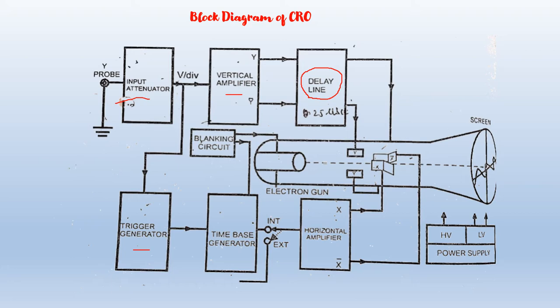The next block is the Time-Based Generator. This produces a sawtooth waveform that is used as the horizontal deflection voltage of the CRT. The rate of rise of the positive-going part of the sawtooth waveform is controlled by the time-per-division knob. The sawtooth voltage is fed to the horizontal amplifier if the switch is in the internal position. If the switch is in the external position, an external horizontal input can be applied to the horizontal amplifier.